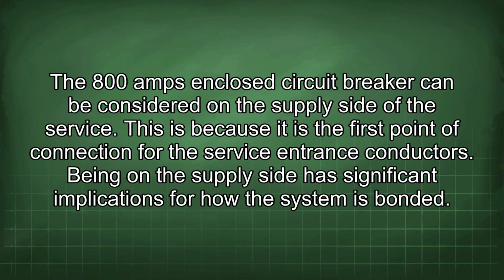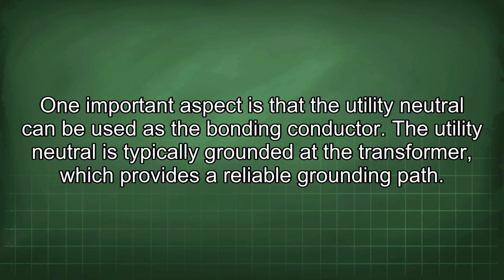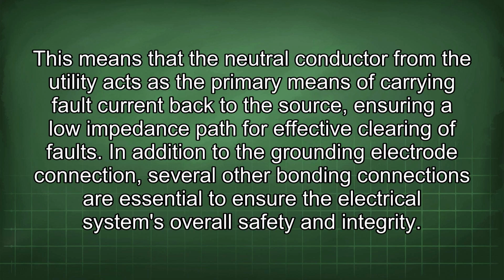The 800 amps enclosed circuit breaker can be considered on the supply side of the service. This is because it is the first point of connection for the service entrance conductors. Being on the supply side has significant implications for how the system is bonded. One important aspect is that the utility neutral can be used as the bonding conductor. The utility neutral is typically grounded at the transformer, which provides a reliable grounding path. This means that the neutral conductor from the utility acts as the primary means of carrying fault current back to the source, ensuring a low impedance path for effective clearing of faults.